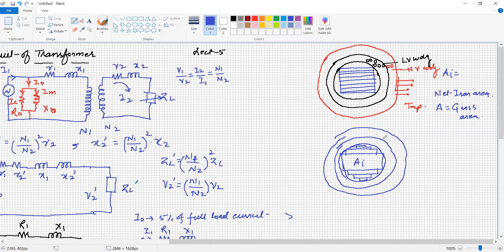Sometimes HV and LV windings are placed on the same limb alternately — LV, HV, LV, HV — in a sandwiching arrangement, which reduces leakage flux and leakage reactance. By analyzing the equivalent circuit parameters and optimizing them, the best performance and cost of the transformer can be achieved. Using more steps makes the circle shape smoother but increases labor and cutting costs. The best compromise between electrical performance and manufacturing cost decides the number of steps in the cruciform core.